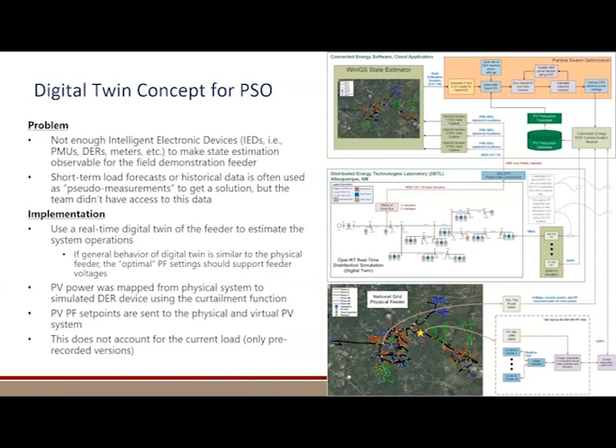And so what we did was a, I think, a little bit clever technique where we used a digital twin. We ran the power hardware in the loop, well, the real-time simulation, at the same time that we were running the field demonstration. To populate the state estimation, we basically pulled the measurements from the simulated PMUs in the real-time simulation as opposed to from the field. We sent that to the state estimator, which was then able to solve, and then we could calculate the optimal power factor set points and issue those to the end devices in the field.